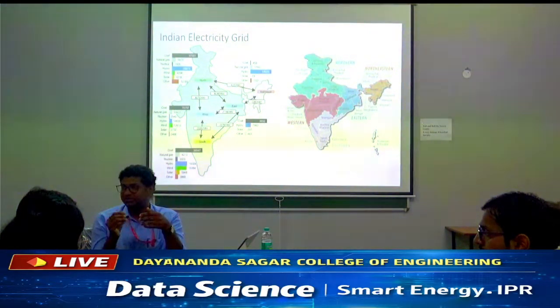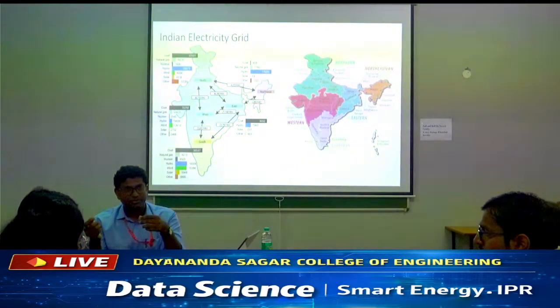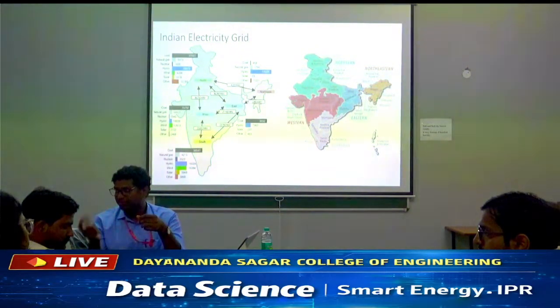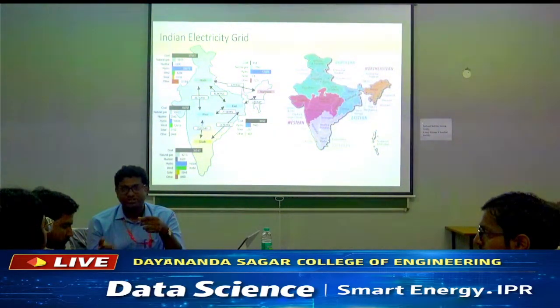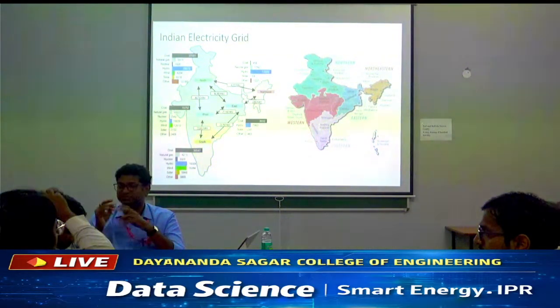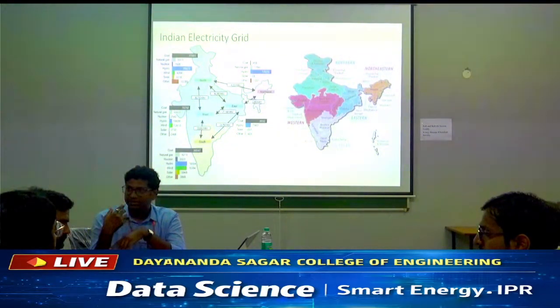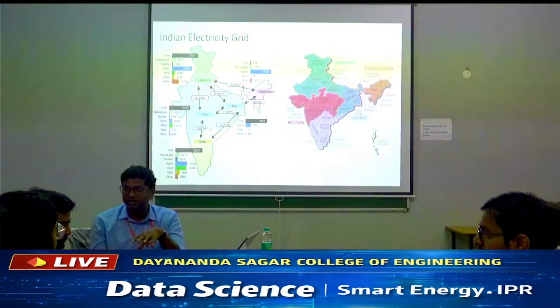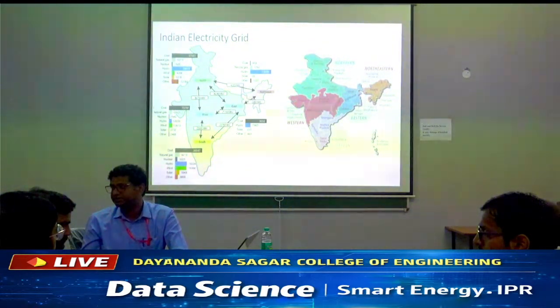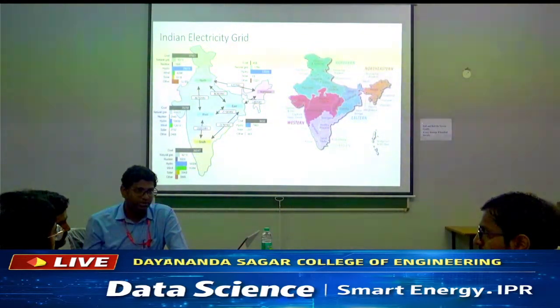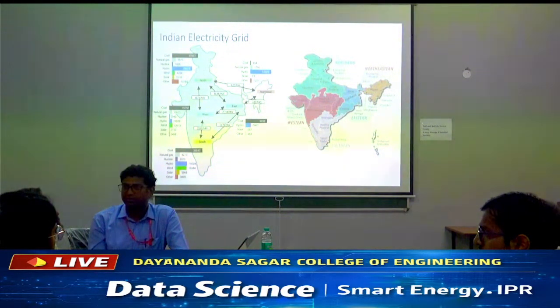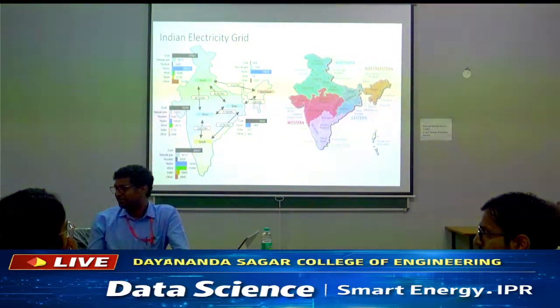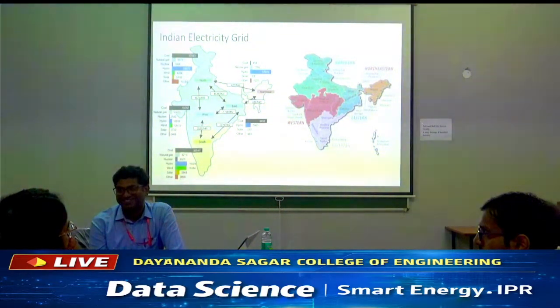So now people are working on how to reduce it to 1 cycle or even half cycle. That means within 0.005, if you are able to predict that this is a fault, then your research is much better than any other. Because throughout, whatever switchgear protections are available, minimum to minimum 1.5 cycle is required to decide whether this is a fault or not. But if you can predict it within half cycle, this is novel work.